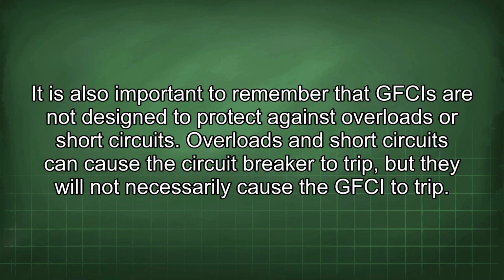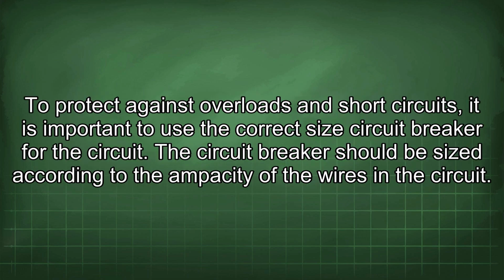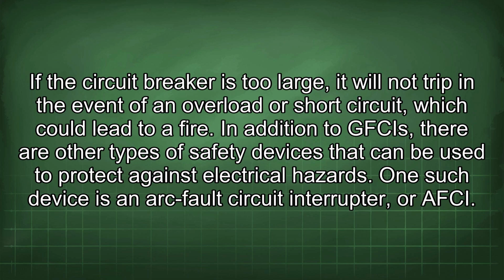It is also important to remember that GFCIs are not designed to protect against overloads or short circuits. Overloads and short circuits can cause the circuit breaker to trip, but they will not necessarily cause the GFCI to trip. To protect against overloads and short circuits, it is important to use the correct size circuit breaker for the circuit. The circuit breaker should be sized according to the ampacity of the wires in the circuit. If the circuit breaker is too large, it will not trip in the event of an overload or short circuit, which could lead to a fire.